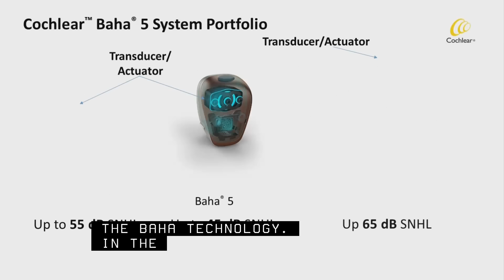In the past, on the first two devices on the left labeled Baha 5 and Baha 5 Power, the actuator and transducer are part of a single integrated component, so it's one sound processor. On the far right, for Baha Superpower, the application we're submitting, we have broken those components apart. It's now not one single component but two: you can see the ear level component, and the actuator and transducer have been separated. I'll explain from an engineering perspective why we had to do that.